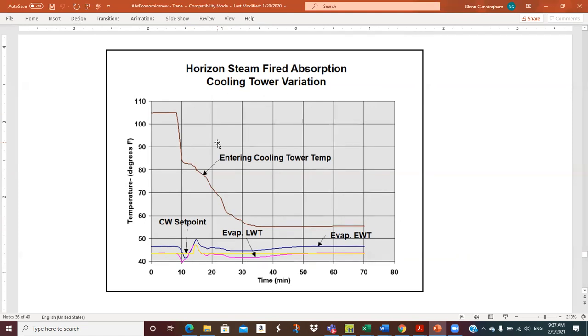And it's pretty impressive that they put it through this rigorous of testing. So what happens, and this is described in these notes down below, is that during the steepest part of this descent, the machine controls just shut down the machine for a short period of time. And so I guess that's in here because you see that, well, now this is on restart. Okay. So we see here's entering water temperature, leaving water temperature.